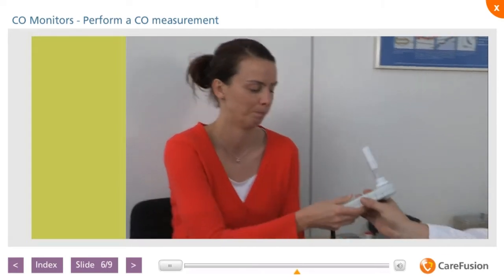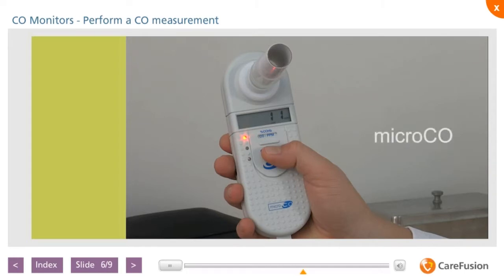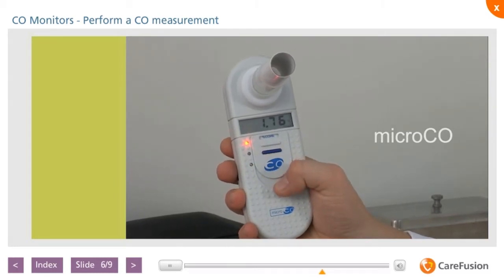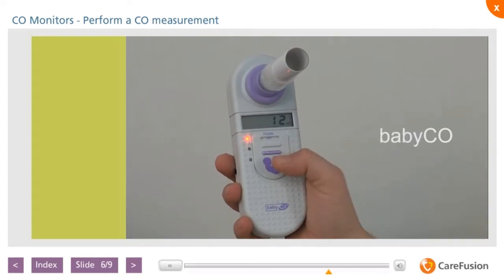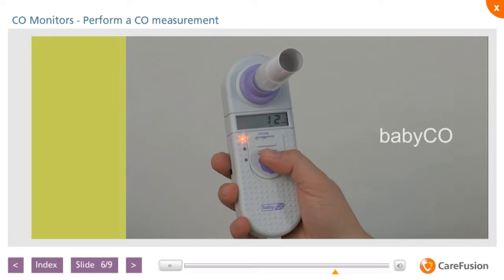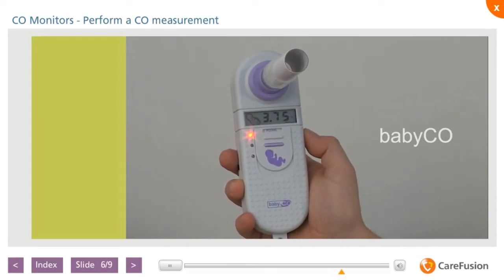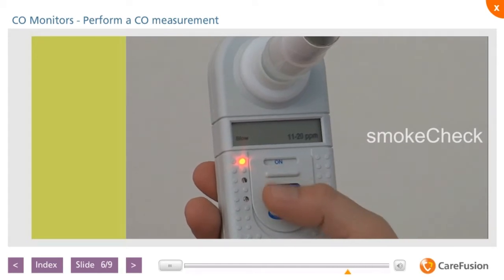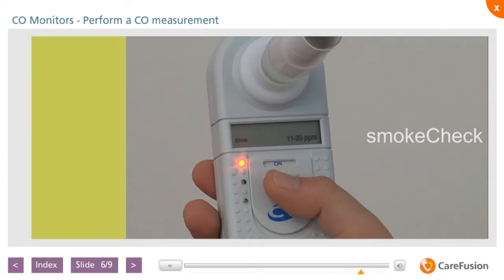The result is displayed directly along with the corresponding LED to indicate non-smoker, light smoker or heavy smoker. In the case of the MicroCO, the unit displays parts per million, and the slide switch can be moved to percentage carboxyhemoglobin. The BabyCO monitor also displays CO in parts per million, and the slide switch can be moved to the fetal carboxyhemoglobin level. The Smoke Check will display the parts per million value measured in one of the four ranges. Range 0 to 6 associated with non-smokers, 7 to 10 associated with light smokers, 11 to 20 associated with heavy smokers, and 20 plus associated with very heavy smokers. Use the MicroCO guide chart to convert the value to parts per million or fetal levels.